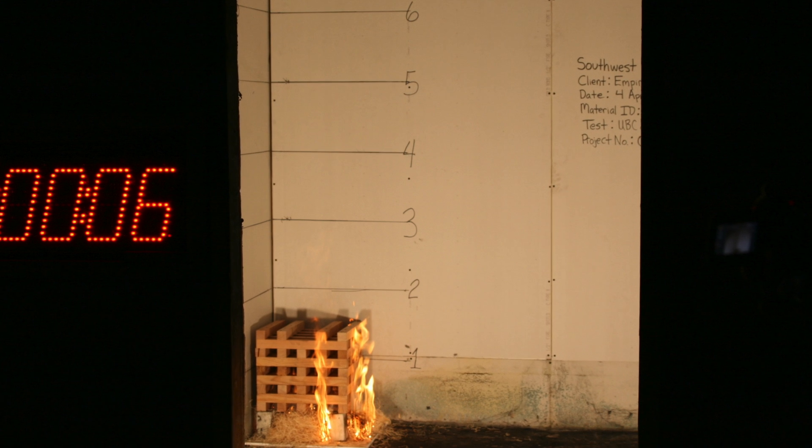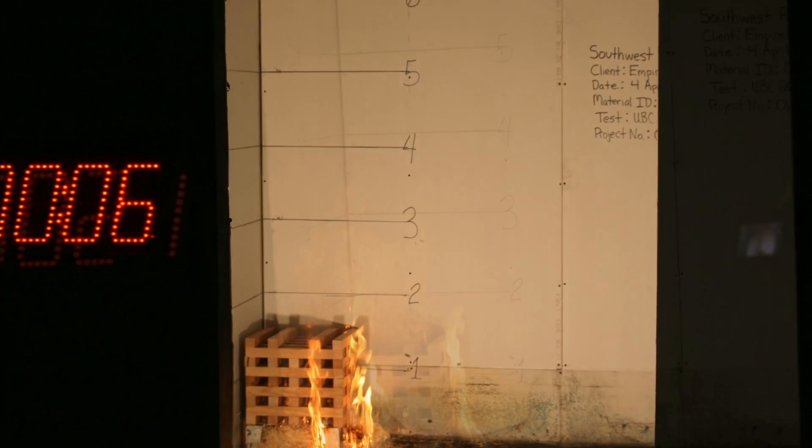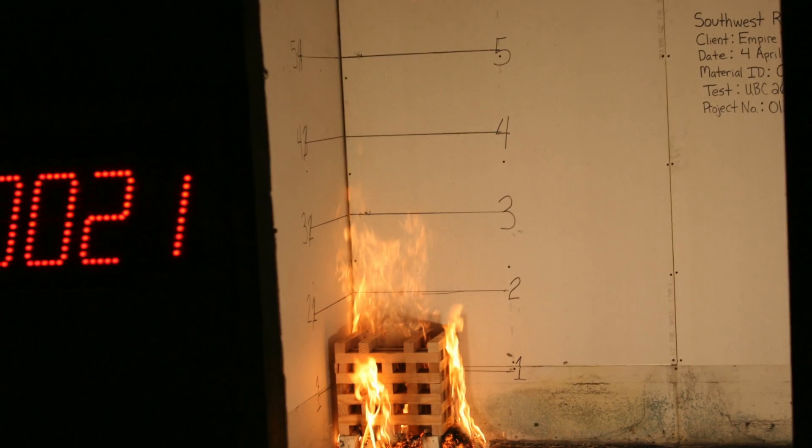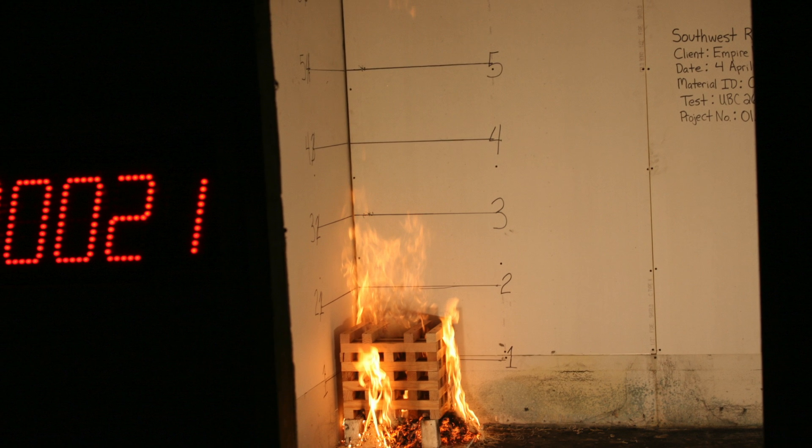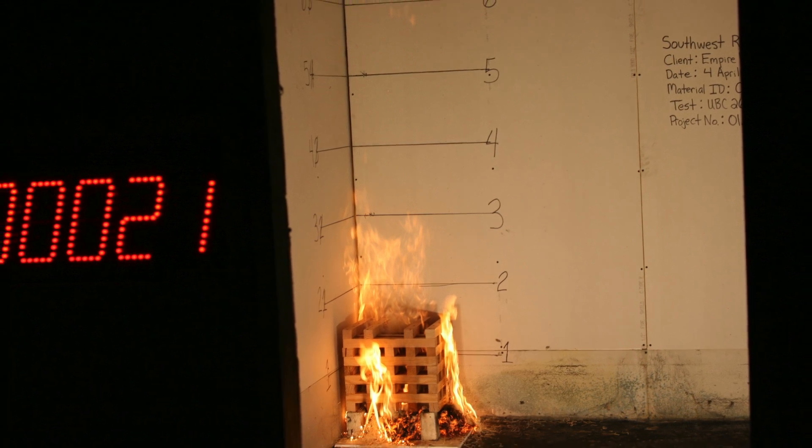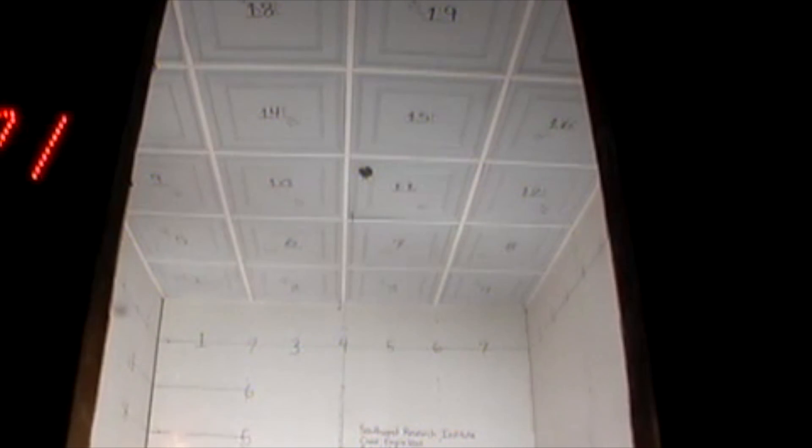When exposed to heat from a fire, dropout ceiling panels distort and release from the grid. They do this at an activation temperature which is lower than that of the sprinklers located above them, giving the sprinklers clear access to extinguish the fire. Panels located directly above the fire distort and fall to the floor very quickly.